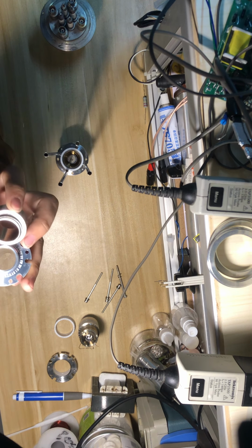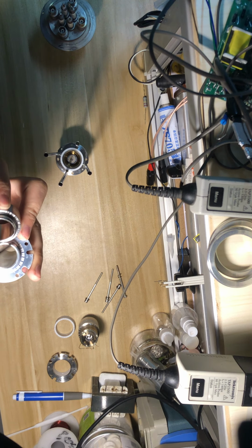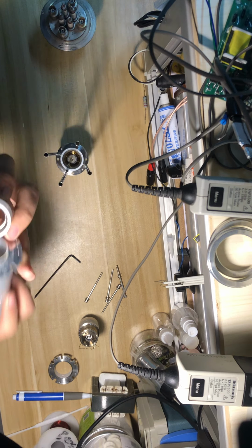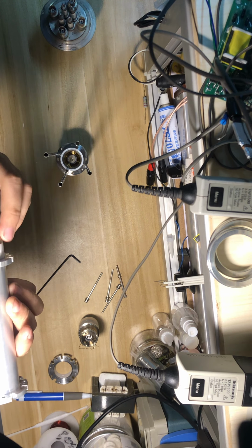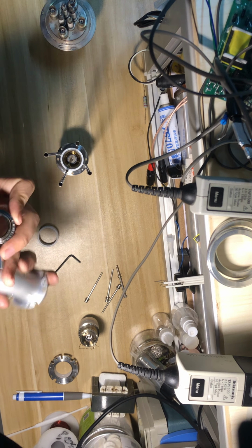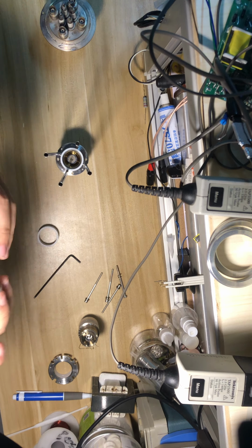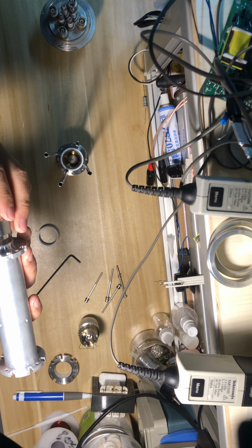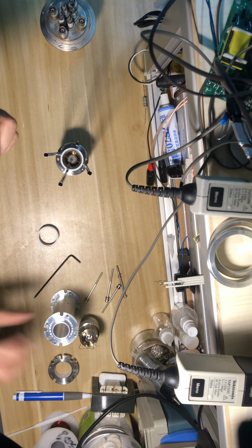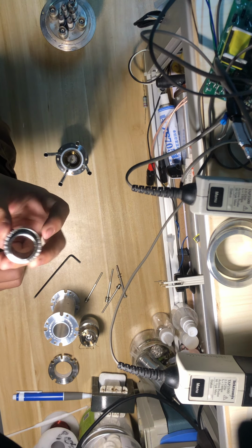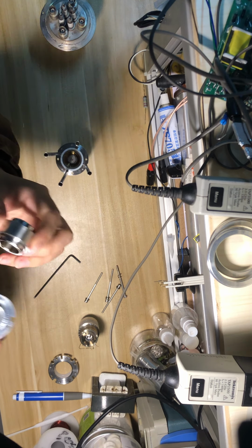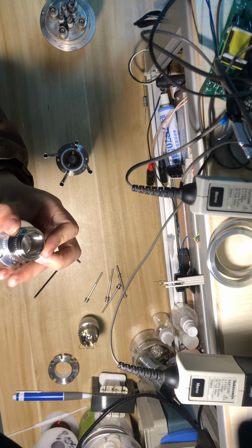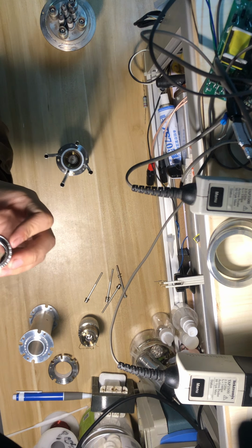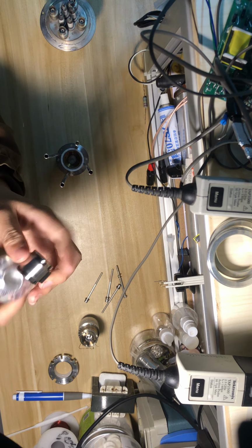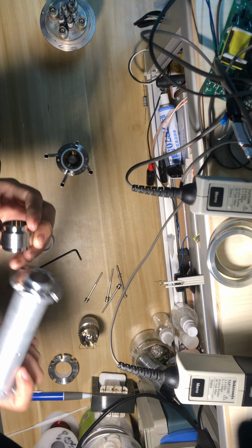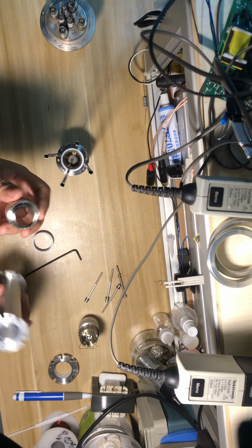Another thing we can see here is that this part and this part are mounted together. You can see they are pretty smooth at the mounting surface. Actually, they are like this. So why are they doing it like this? It's because the electric field is very high between these two electrodes. If there's another rough surface, you get a spark, so it will discharge between these two electrodes. So basically this is the focus ring.